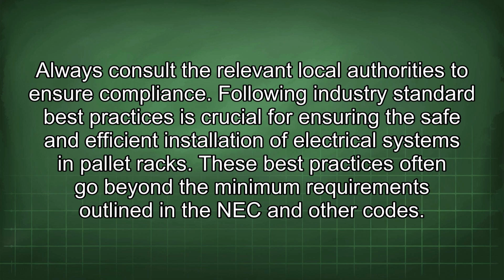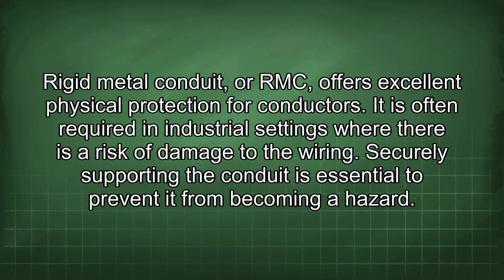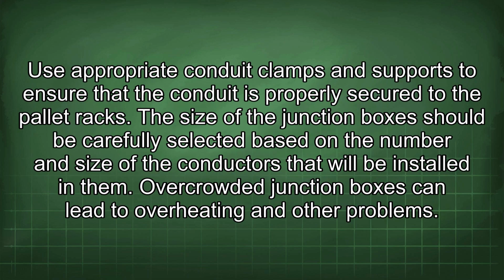Following industry standard best practices is crucial for ensuring the safe and efficient installation of electrical systems in pallet racks. These best practices often go beyond the minimum requirements outlined in the NEC and other codes. Rigid metal conduit, or RMC, offers excellent physical protection for conductors. It is often required in industrial settings where there is a risk of damage to the wiring. Securely supporting the conduit is essential to prevent it from becoming a hazard. Use appropriate conduit clamps and supports to ensure that the conduit is properly secured to the pallet racks.